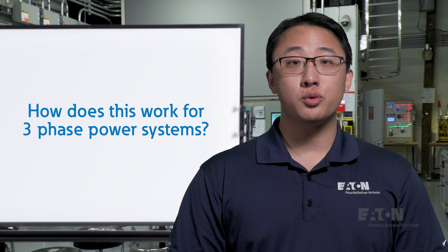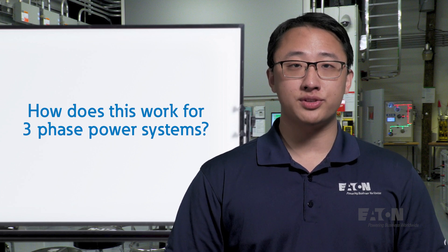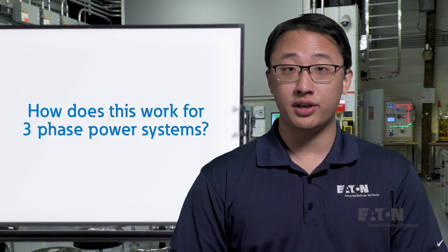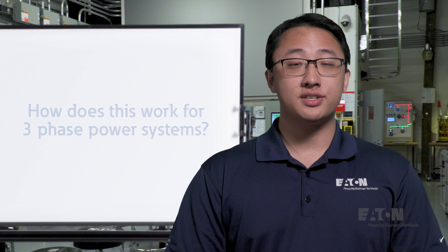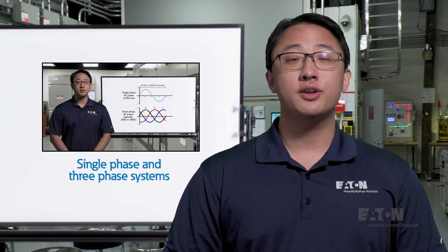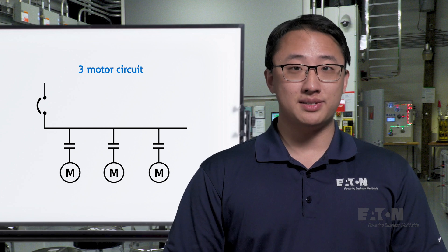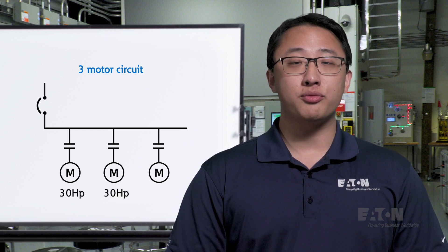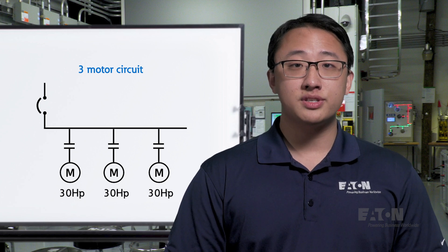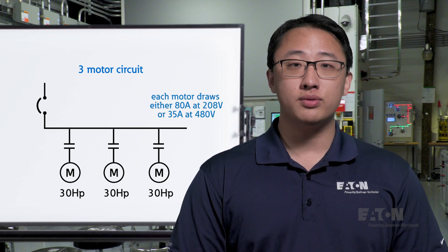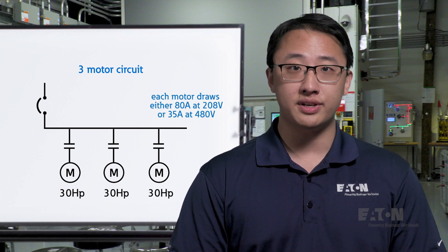The previous examples we used were with single-phase power in a residential setting, but most larger-scale power systems, like in industrial and commercial applications, will require three-phase power. Now let's bring it all together and design a system. The goal is to power three pre-chosen 30-horsepower motors. The nameplate data for the motors says they draw 80 amps at 208 volts, or 35 amps at 480 volts, to feed chillers in a commercial facility.